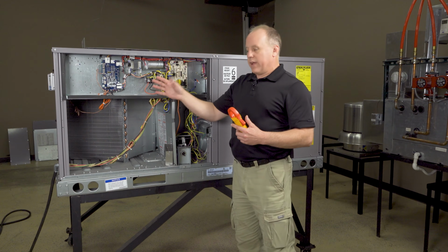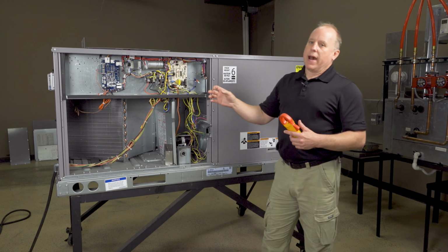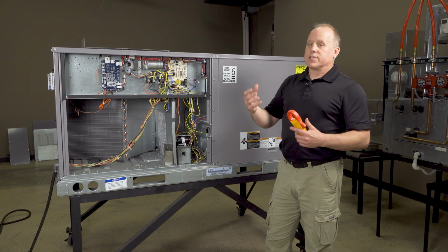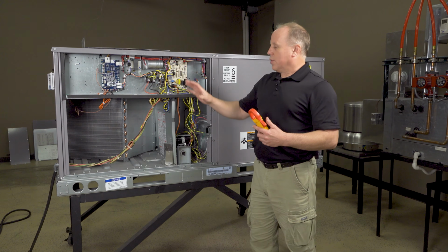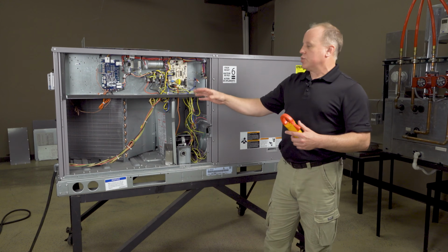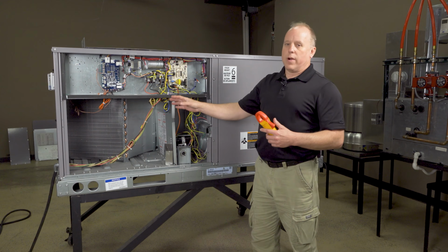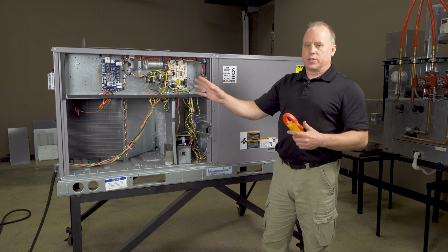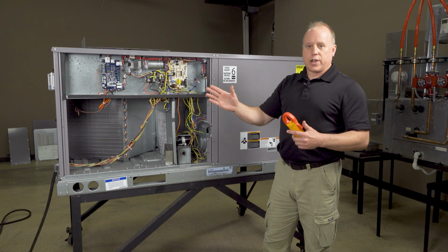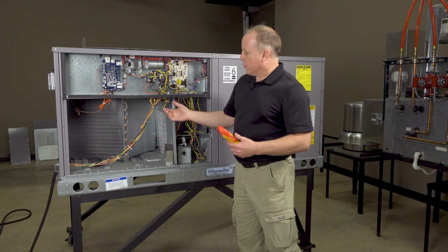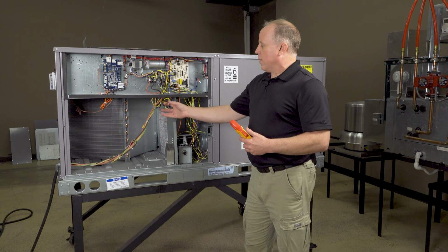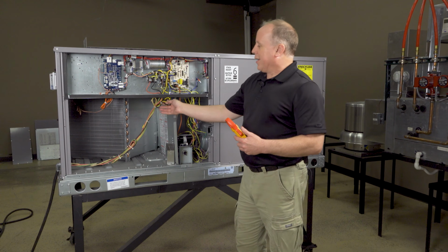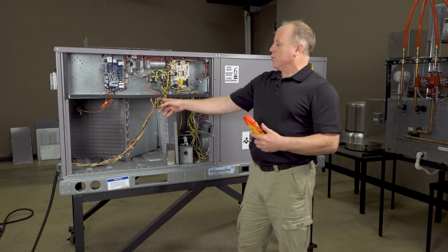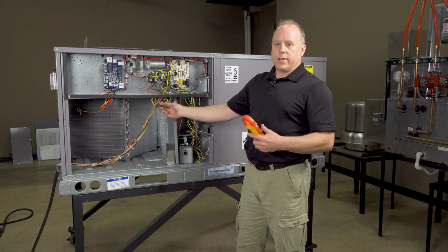Always when we're doing this, we have to be careful. The unit is powered, so when we're taking our amp draws, obviously it has to be operating. So whenever we're reaching in, we want to make sure we know where we're going with the wires and we're in an area where we're not going to be touching anything that could be a shock issue. So first off, we're going to get the wires right in front here. I've already kind of gone through this, and I know for sure that these are condenser fan wires.